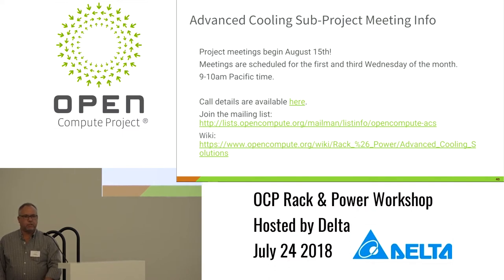Do you guys have any questions about what we're doing, why we're doing it? What is the typical wattage level at which this advanced cooling kicks in, or what's the threshold? Is it 3K, or how does it get distributed? Well, good question. You heard discussions earlier around at what point air cooling becomes ineffective, and maybe it's in the 30 to 50 kilowatt range.